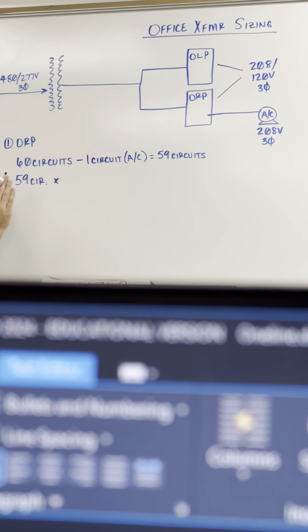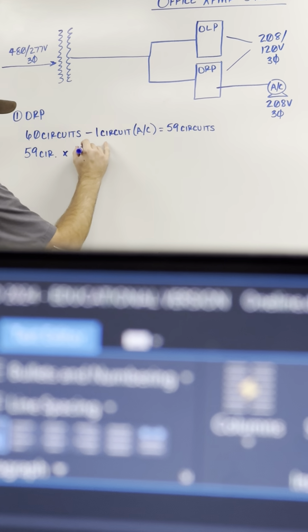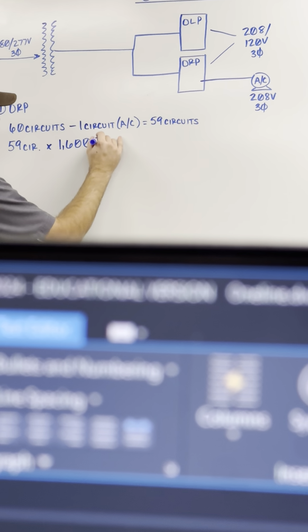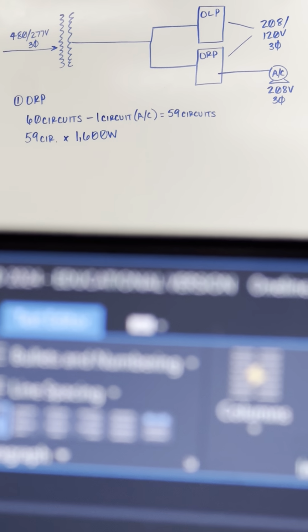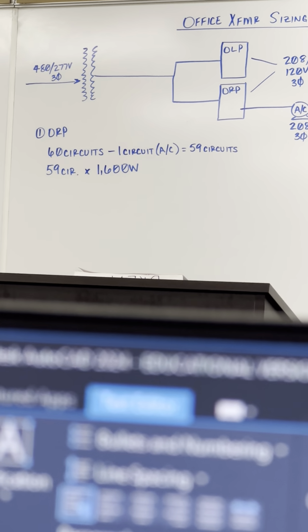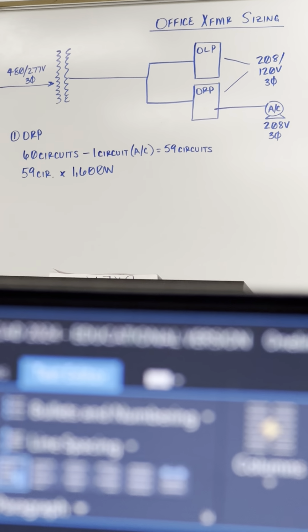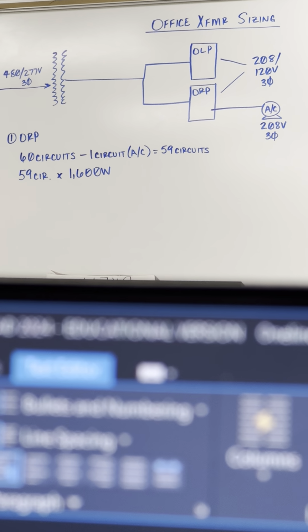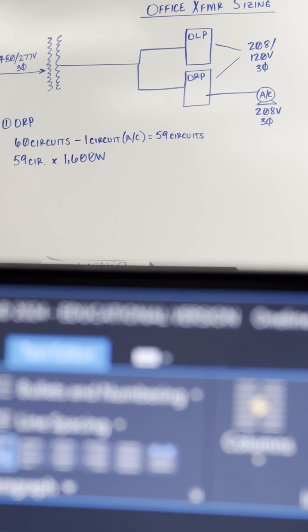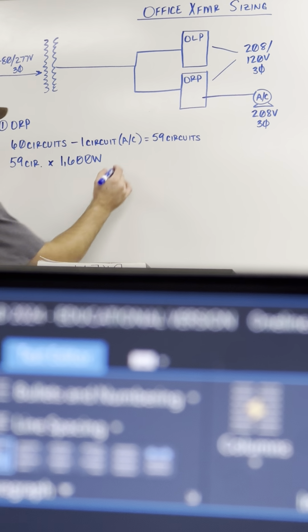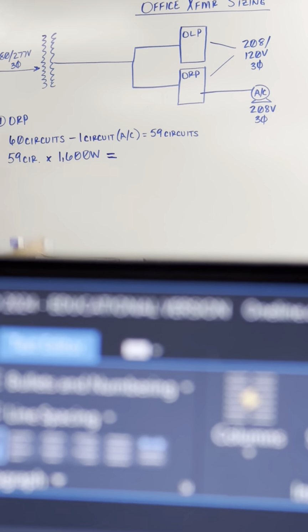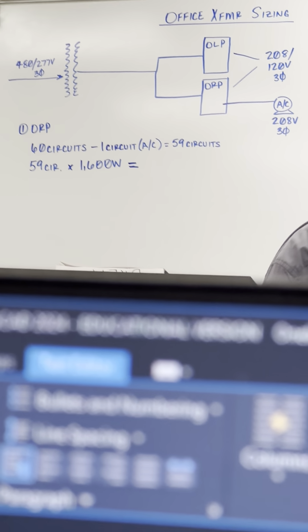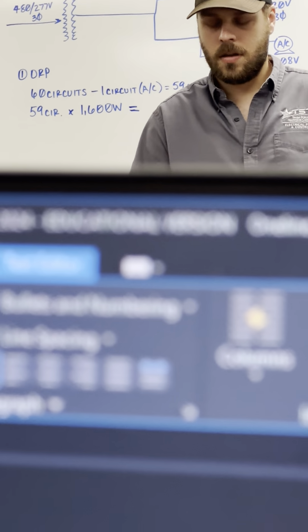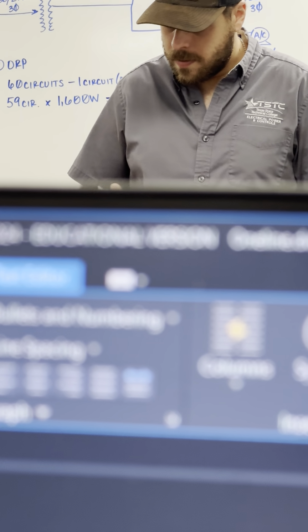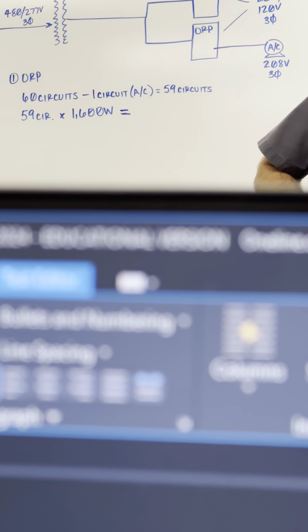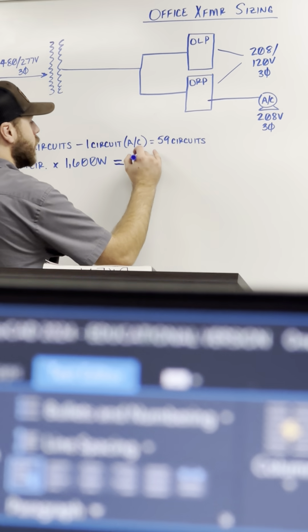So it's a very similar process. We'll take 59 circuits and we'll take 1,600 watts for the maximum wattage on there. And even if all your receptacle circuits don't have 4 receptacles on them in the office, that's fine. We'll chalk that up to future expansion. So if you had a circuit that only had 2 receptacles on it, for example, we might come back in the future and add 2 more to that same circuit. So we're just gonna do everything at 1,600 watts. So we take 59, multiply it by 1,600. I get 94.4 kilowatts.